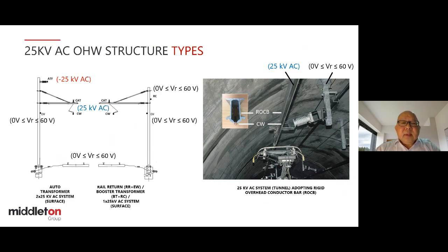In the middle is actually a hybrid. So you've got the contact wire, catenary, running rails, and then the earth wire. The earth wire is bonded to the running rails, and the structure is actually used as a mini earth rod along the track to give you your distributed earthing system. And for the booster transformer, there's a return conductor up there as well.